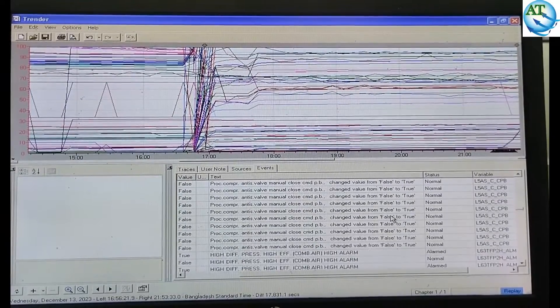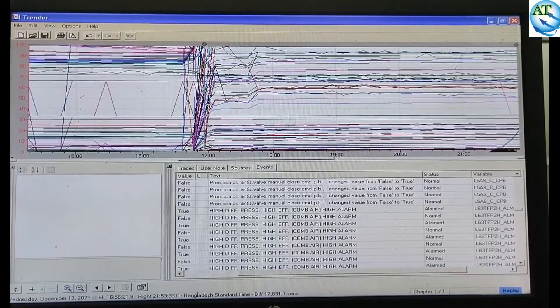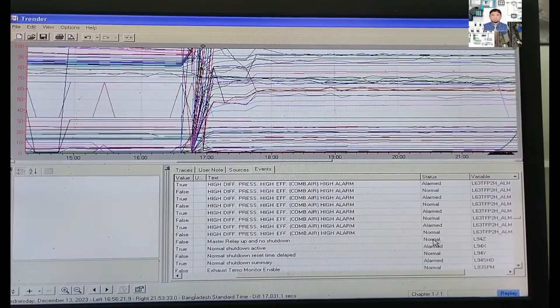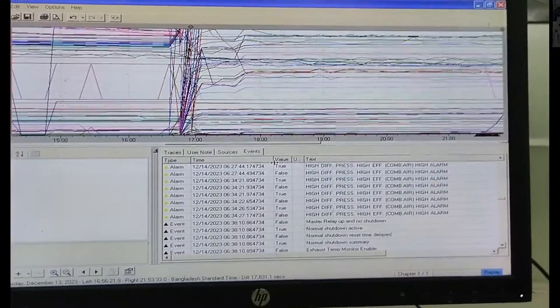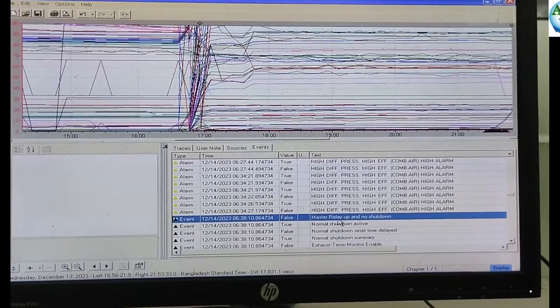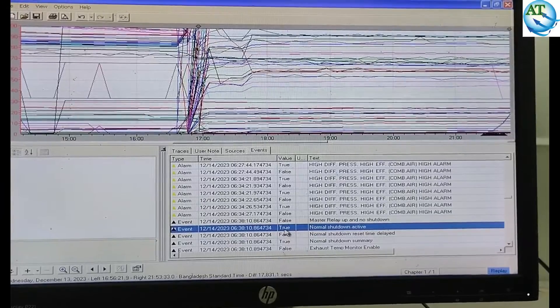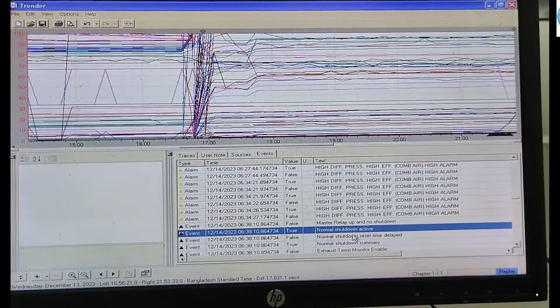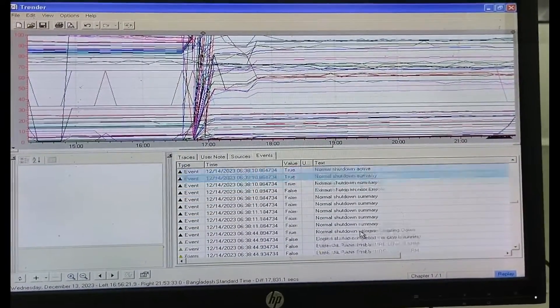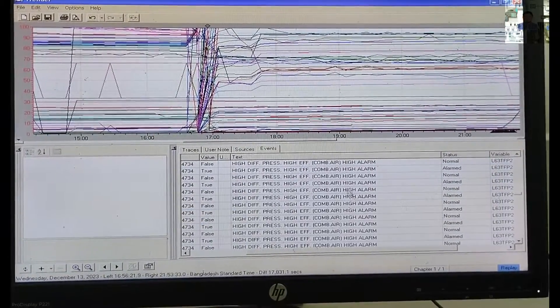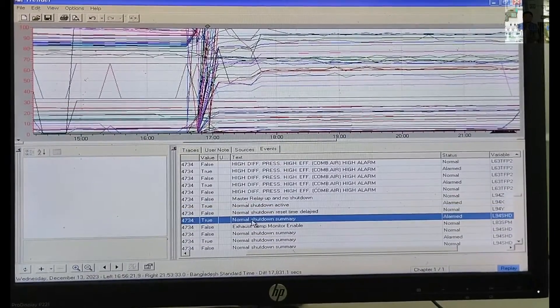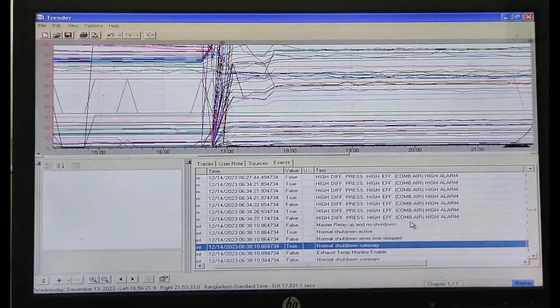For this data, one is TRIP. You can see from here — some alarms are coming: alarm acknowledge, alarm come and acknowledge, alarm come and acknowledge, the TRIP and event data. Here you can see the master relay up and no shutdown. One alarm is showing, and another one is showing — normal shutdown activation. You can see: normal shutdown active. The time is 6:38. At 6:38, the turbine has an alarm — normal shutdown activated and the turbine TRIPped. From here you can understand for that reason the turbine TRIPped. When the normal shutdown activates, all the parameters come down. It is the normal shutdown active — step by step the turbine stops. The turbine is STOP, not TRIP. It is a STOP. So the main cause is that the normal shutdown activated in the software.